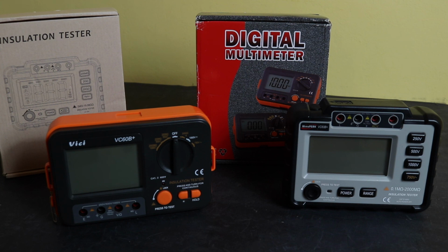Outside of that, if you just want an insulation tester to play around with, then they do offer that opportunity. If you're testing something that is perfectly okay, it will tell you that. If you're testing something that has failed insulation wise, it will tell you that as well. The problem will come where you're testing something that's borderline, and neither of those two units are capable of putting out the required output under those scenarios. So whereas a tester that could put that output out may lead to failing the device that you're testing, these testers might well actually pass it because they can't put out the right voltage and current on those borderline cases. So just a play around meter for me as far as I'm concerned.